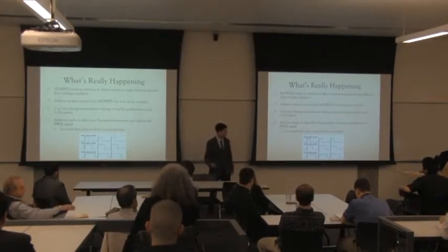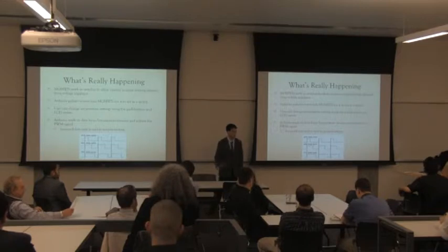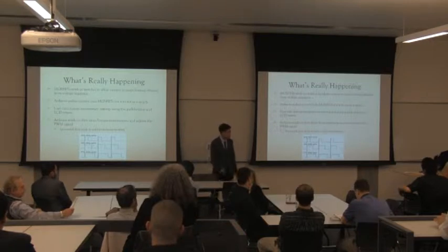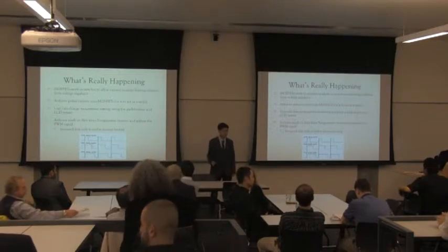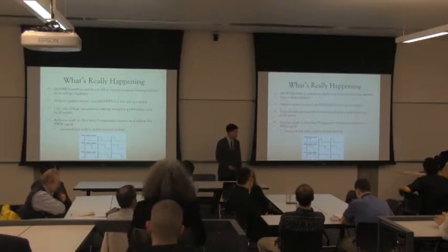By increasing the duty cycle, we are increasing the amount of time that it is on, therefore increasing the average power delivered to each of the heating elements. This is how we can increase heating. Once the desired temperature setting has been met, we then decrease heating in a similar manner by decreasing the duty cycle.